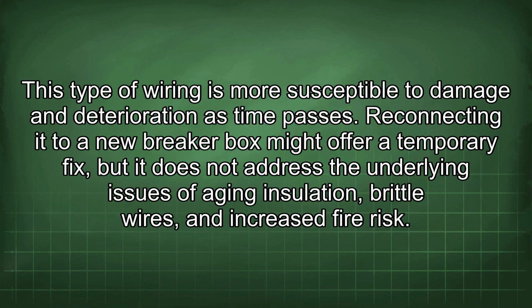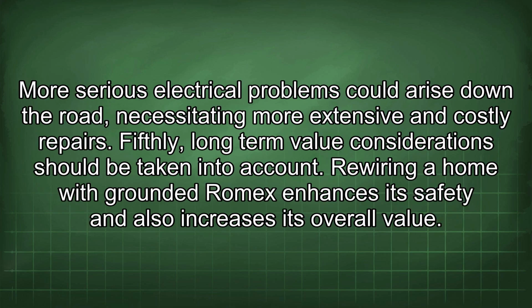This type of wiring is more susceptible to damage and deterioration as time passes. Reconnecting it to a new breaker box might offer a temporary fix, but it does not address the underlying issues of aging insulation, brittle wires, and increased fire risk. More serious electrical problems could arise down the road, necessitating more extensive and costly repairs.